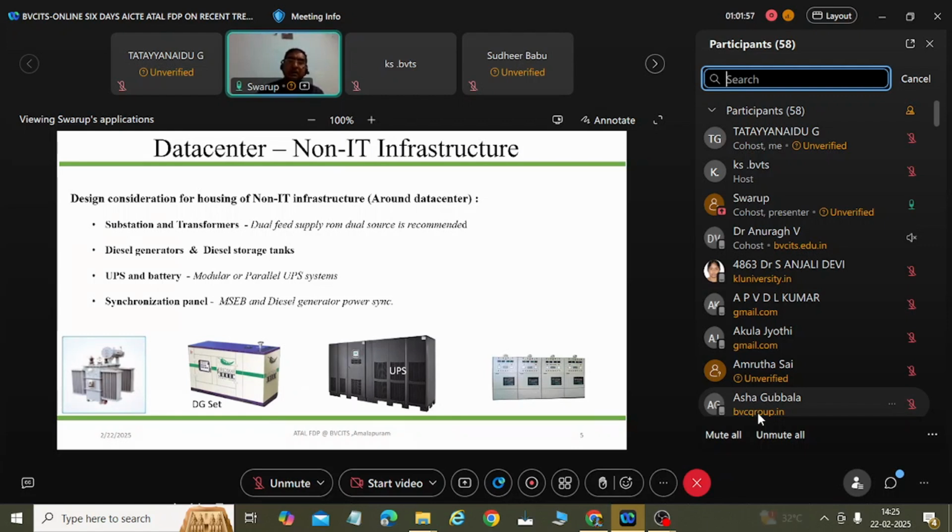It takes another minute to take the entire load. So that is why I don't need a huge battery backup, because say in 20 minutes, if the DG set is not going to come up and another source is not going to come up, then system administrators will have their own way of shutting down the systems, because ultimately everything is cost.